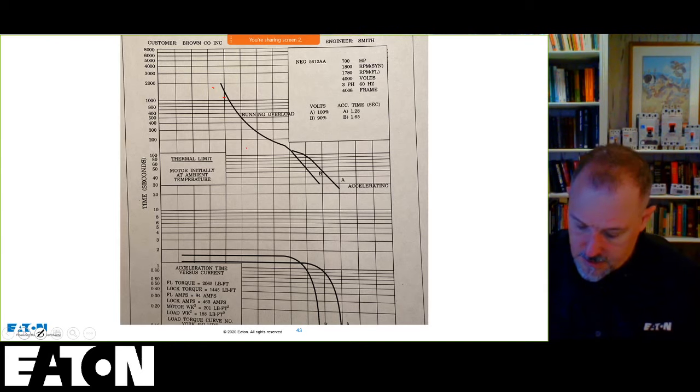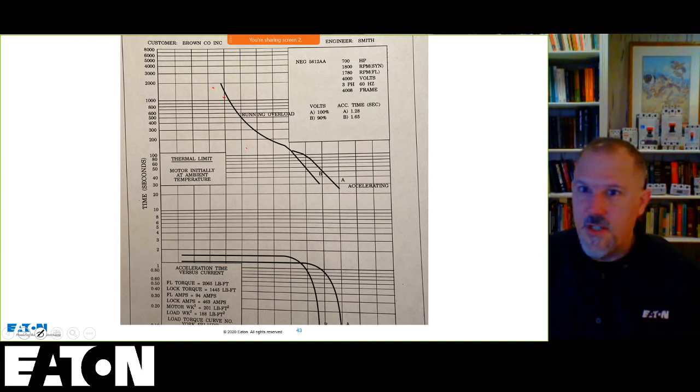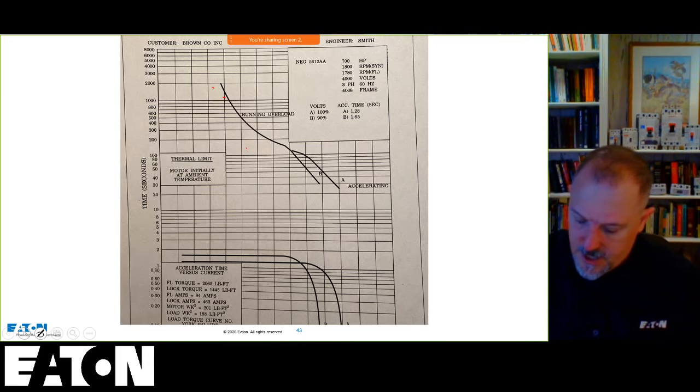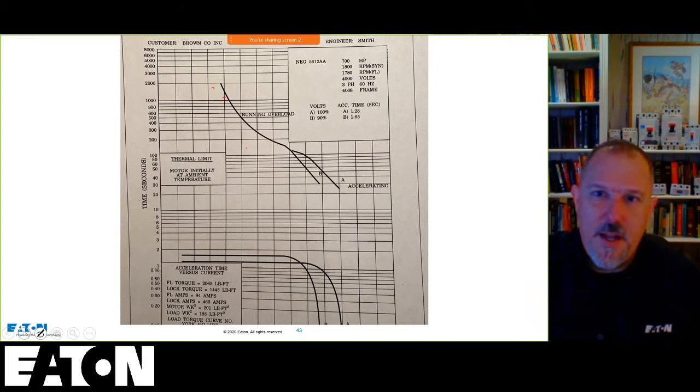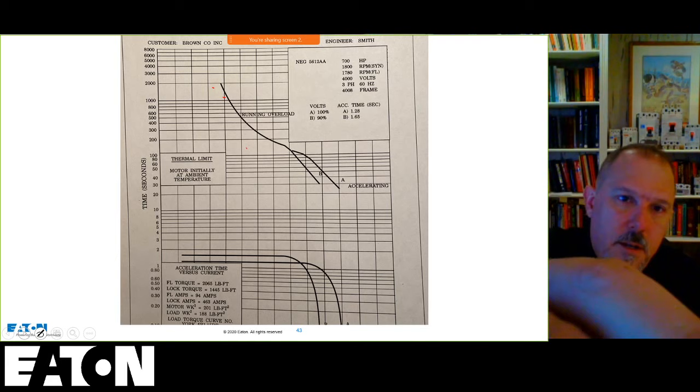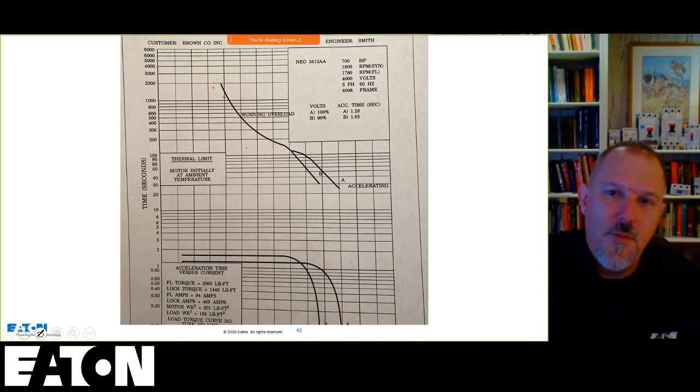And this one here actually calls out, and I'm not sure if I have it, but it calls out that the acceleration time for this is around, at 100% voltage, around 1.3 seconds. At 90% voltage, it's 1.7 seconds. And then you have the damage.